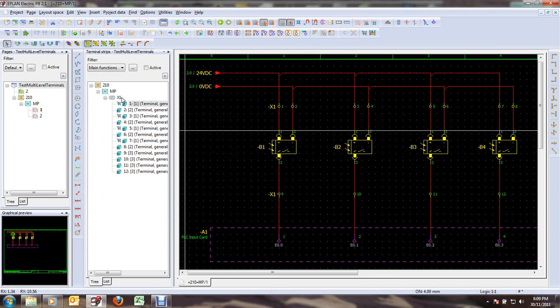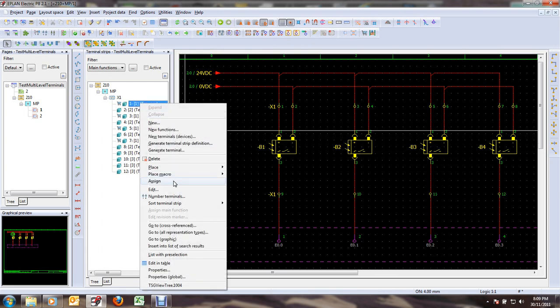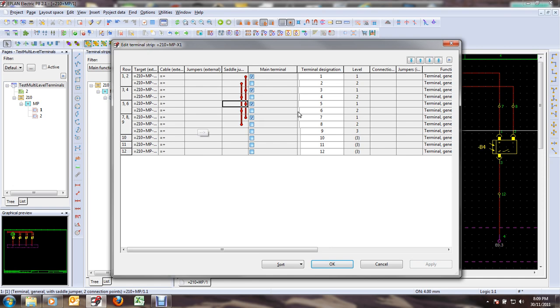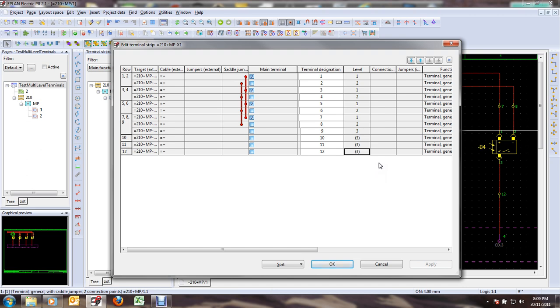If I look again at my navigator and edit my terminal strip, I notice something here. I have my levels one and two, one and two, and so on, and then all my level threes are at the end, which is not really what I want. In order for EPLAN P8 to handle multi-level terminals, we need to have them in a consecutive fashion.